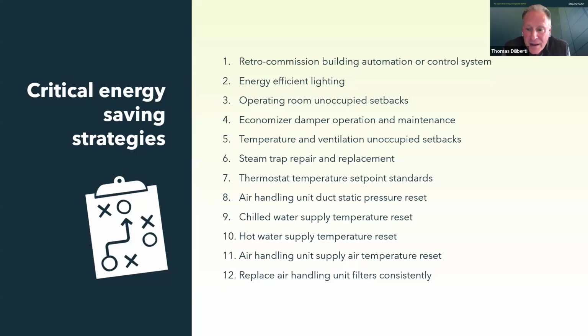Numbers 9, 10, and 11 are really the same idea as number 8 - a reset, meaning chill water or hot water changes based on need. Take chill water, for example: it's used to cool our facilities, so it's needed during hot weather. But the hottest day of the year only occurs once a year, and the system needs to be set to accommodate that hottest day so the building can be air conditioned and people can be comfortable.